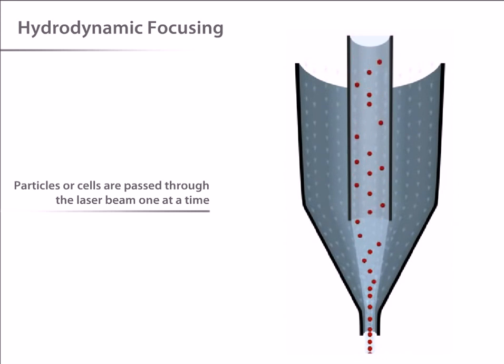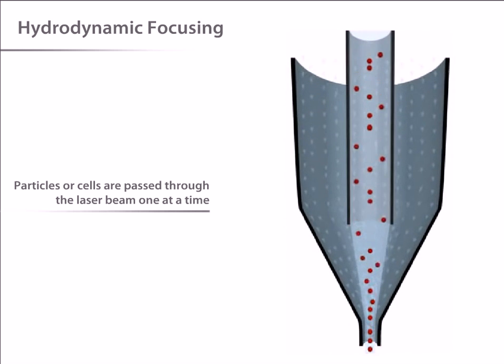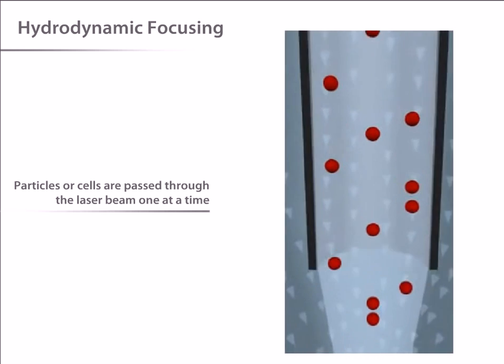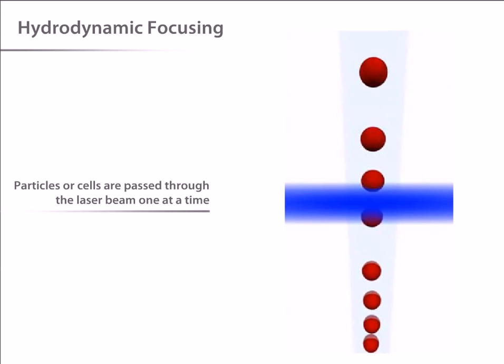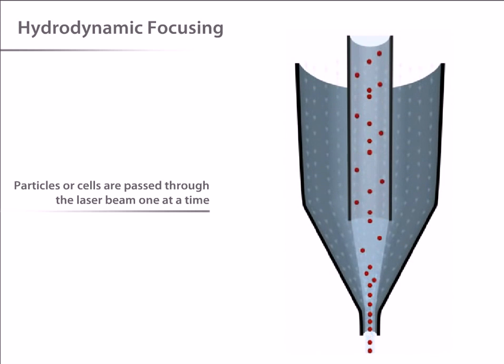Most flow cytometers accomplish this by injecting the sample stream containing the cells into a flowing stream of sheath fluid or saline solution. As you can see, the sample stream becomes compressed to roughly one cell in diameter. This is called hydrodynamic focusing.